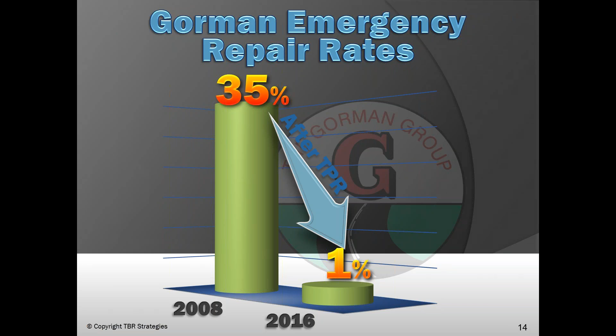Now, how do we do that? Well, one of the things we had to do is get them away from the emergencies. And here's a perfectly good illustration of how it was. In 2008, they were spending about a third of their maintenance activity on emergencies. That's 1/3 of their total maintenance hours. By 2016, we got it down to 1%. And that's where they are today, between 1% and 2%. They like to keep it less than 2%. That means 98% of their activity is basically planned and scheduled. They have a planner and a scheduler, and those people plan the corrective maintenance and preventive maintenance activities to prevent these emergencies from occurring.